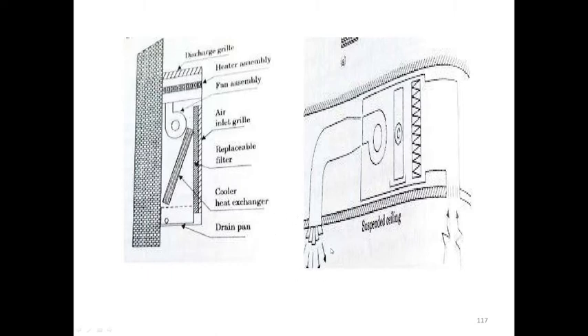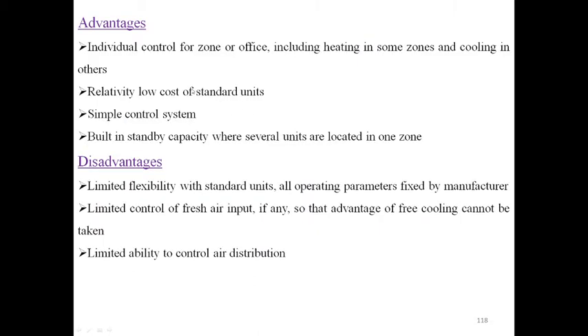The ceiling distributes cooling air so all people in the room receive cooling. Advantages of fan coil systems include: individual control for each zone or office, including heating in some zones and cooling in others; relatively low cost of standard units; simple control system; and built-in standby capacity where several units are located in one zone.